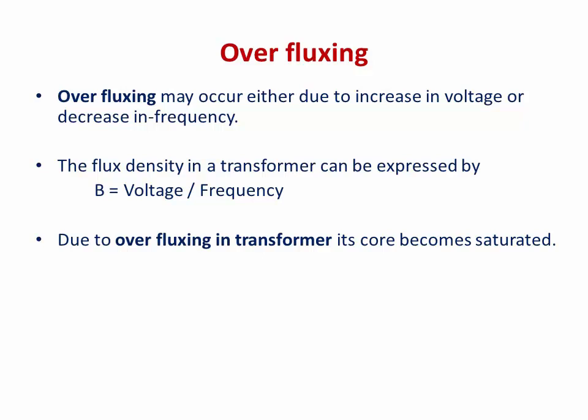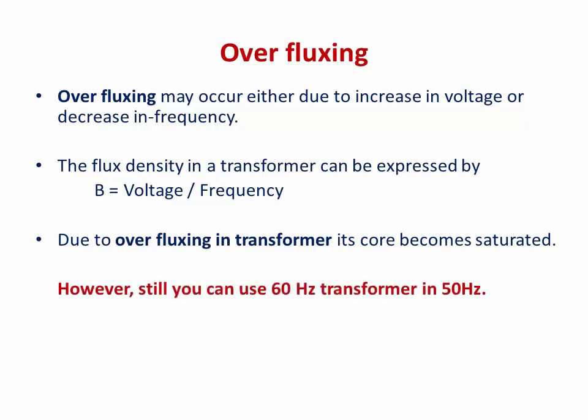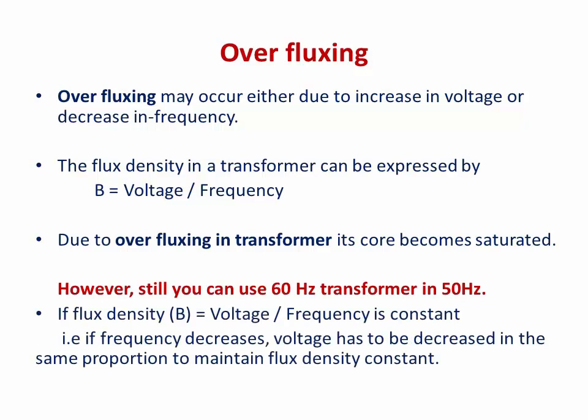How do we do that? If we keep V/f constant — that is, flux density in the transformer is constant — you can still use a 60 Hz transformer on a 50 Hz supply. If the frequency decreases or increases, the voltage must be decreased or increased in the same proportion to maintain the same flux density. If you do so, you can operate a 60 Hz transformer on a 50 Hz supply source.